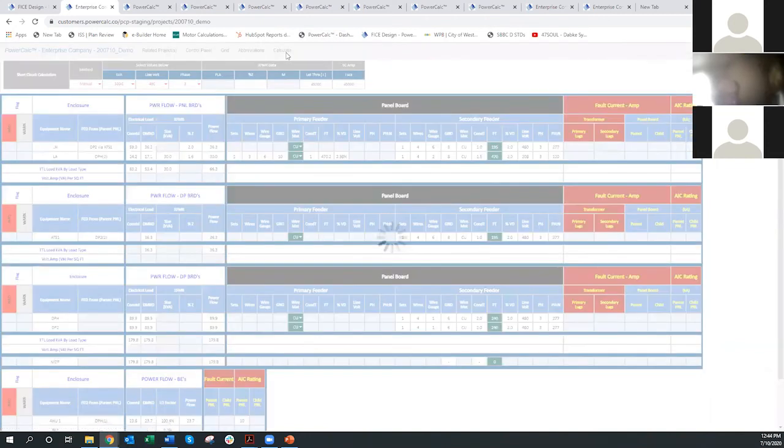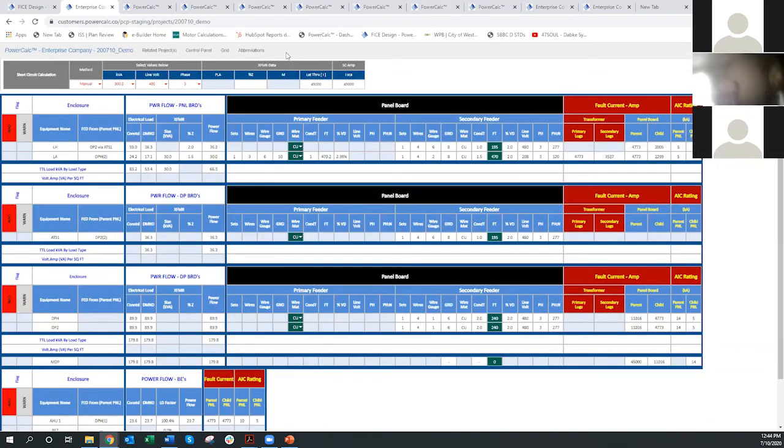All right, so it calculated on my MDP. It was 45,000. By the time it traveled to the MDP, it dropped down to 11,000. And then that 11,000, when it went to DP2 down here, it dropped down to 4773 and so forth. Now, this said it's not that far away, but actually it shows a zero, so it's an infinite. So let's say that actually the transformer is about 100 feet from MDP. So we're going to change it to 100 feet, recalculate.